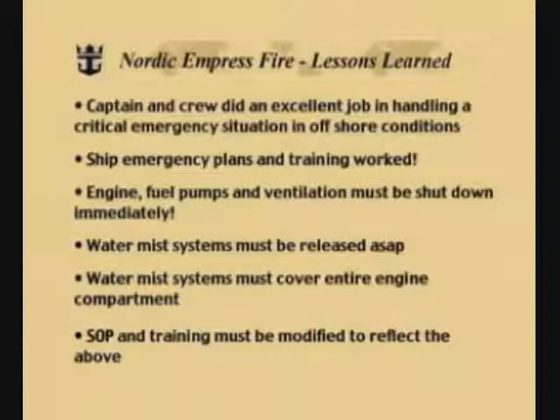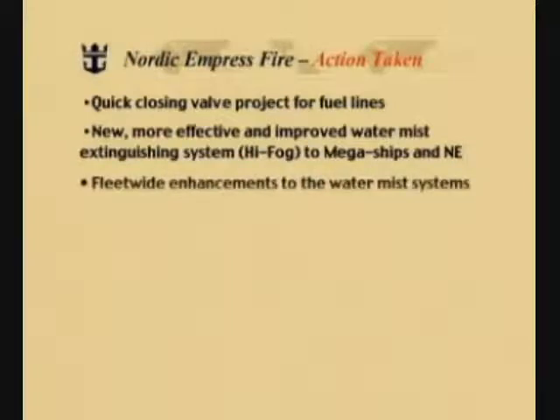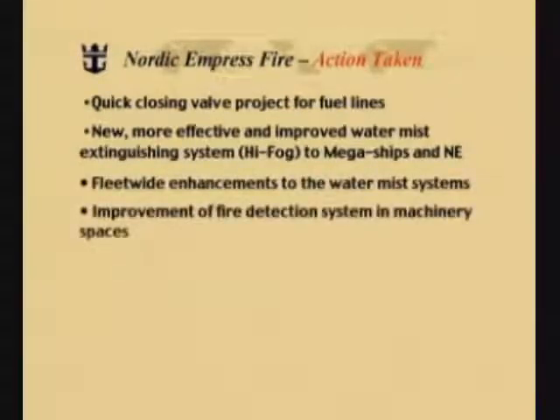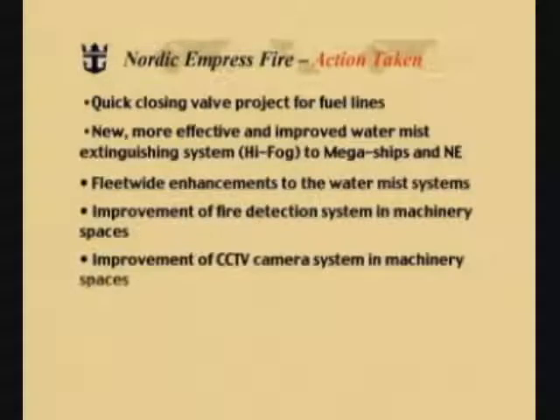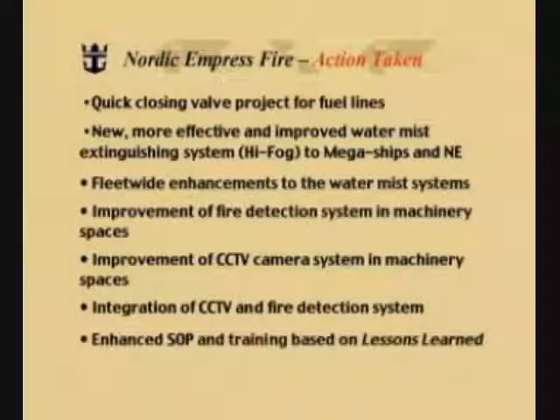The important thing with lessons learned is to take action. And action was taken after the fire. A quick-closing valve project was established for fuel lines. New, more efficient and improved water mist extinguishing systems — Hi-Fog — were installed on the megaships and the Nordic Empress. Fleet-wide enhancements to the water mist systems already installed were made. Fire detection systems and closed-circuit television camera systems in the machinery spaces were improved. Closed-circuit TV and the fire detection system were integrated. Enhanced standard operating procedures and training were implemented based on the lessons learned. In total, over $3.8 million in upgrades.